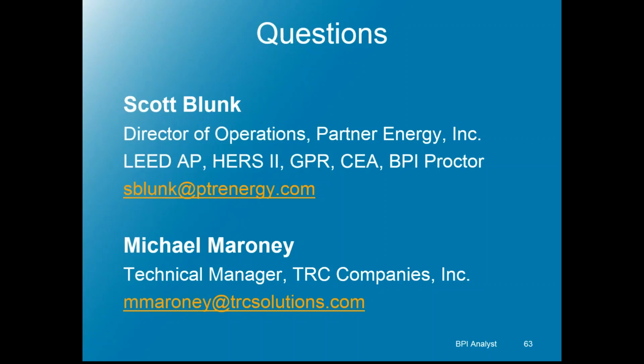Great, yeah, thanks for getting into that. And from my perspective, working on the program side, we often see, as Scott was saying, the one-for-one, like-for-like change-out. And that's often not the case, but it's a tricky sell to try and incentivize or influence any HVAC contractor to actually do the legwork to right-size the equipment. Because ultimately the liability or the complaints are going to be on the contractor. The energy benefit is oftentimes much less important in the single-family world than the comfort that the tenant or the homeowner feels from an HVAC system that they perceive to be working more effectively, because typically the bigger systems will just cool them off faster. But that gets into a whole other bag of worms.